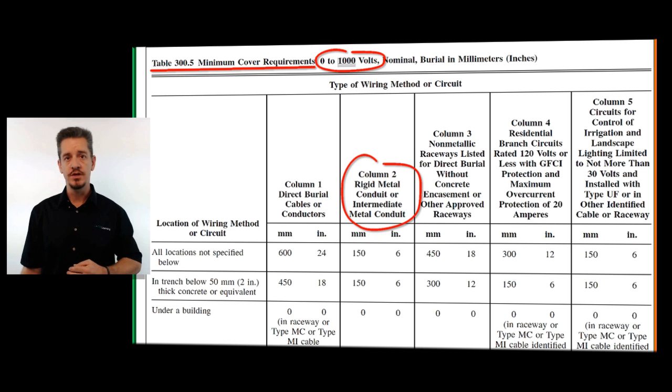That's whenever you're outside underneath of four inches of concrete and your concrete extends at least six inches on each side of your metal raceway. But in most circumstances, it's going to be six inches.